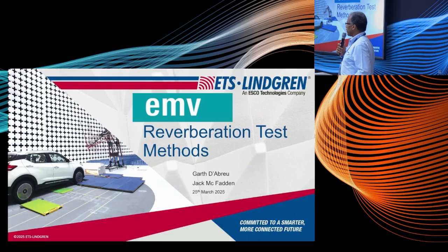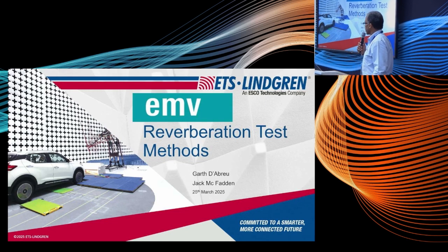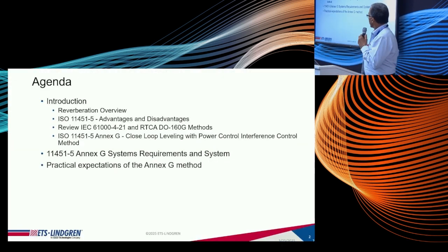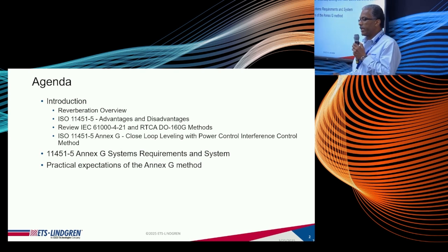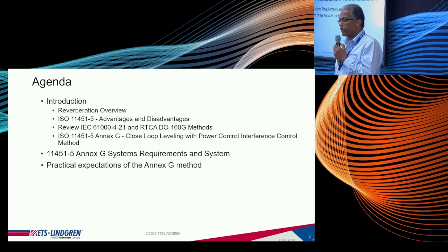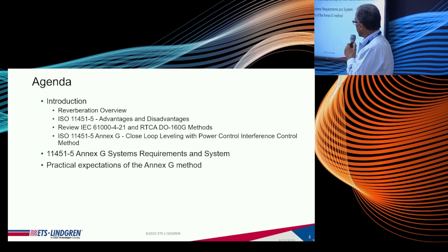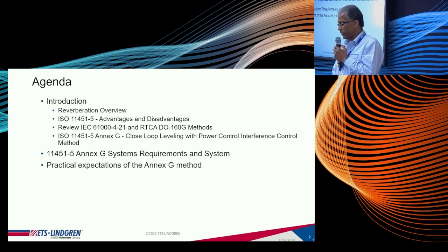Okay, I'm going to talk about the immunity side of reverberation chamber testing. And specifically, I'm going to look at some actual test results following one of the new reverberation chamber standards, and how that compares to some of the other existing reverberation chamber standards. So I'll talk a little bit about the IEC documents, 61000-4-21, the DO-160 standard, and the procedures used in those two documents, and see how that compares to the new techniques suggested in the ISO 11451-5 standard that we will probably see in the 452-11 standard as well, sometime in the very near future.